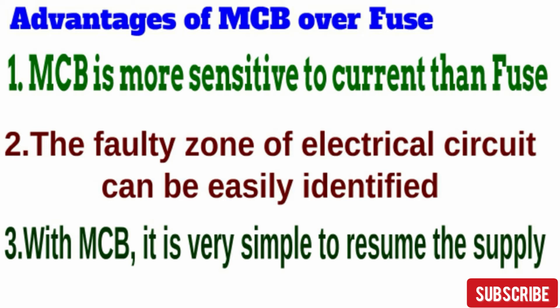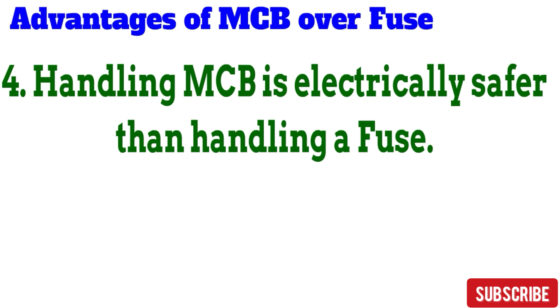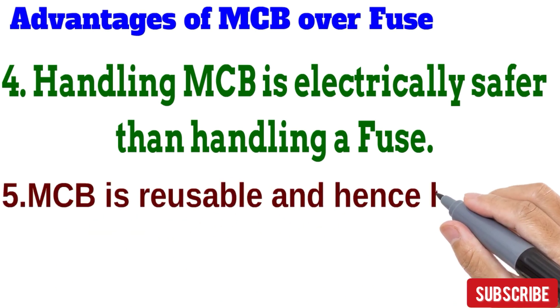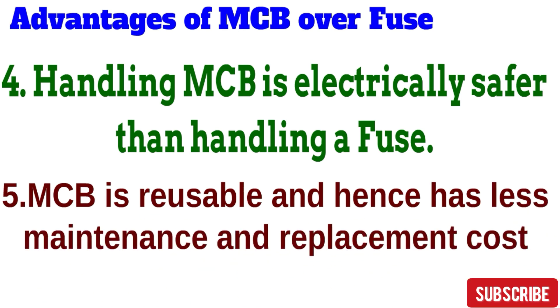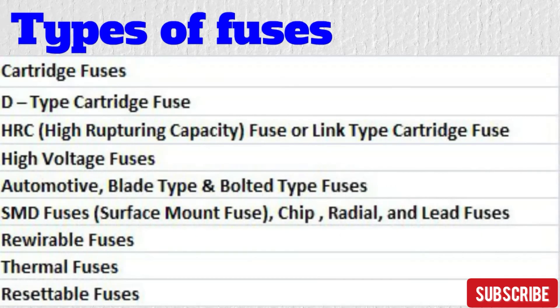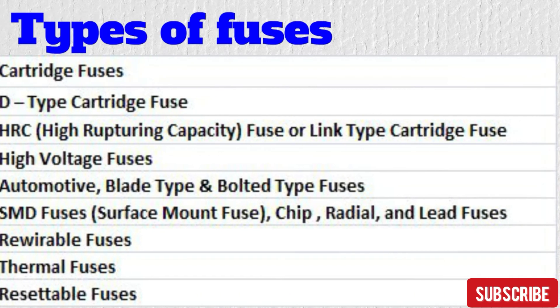Third, an MCB is very simple to resume power supply — if it has tripped, you just need to push the knob back to the on position. With a fuse, the entire fuse wire needs to be replaced. Fourth, handling an MCB is electrically safer than handling a fuse — the user is not exposed to live electrical parts, whereas replacing a fuse carries a risk of contact with a live wire. Fifth, the MCB is reusable and therefore has less maintenance and replacement cost, whereas a fuse must be replaced whenever it goes faulty.